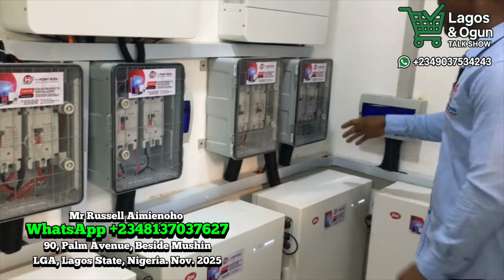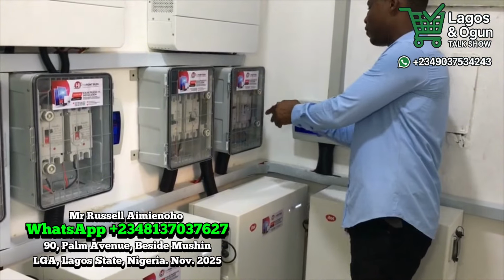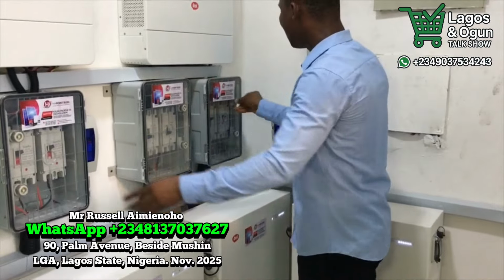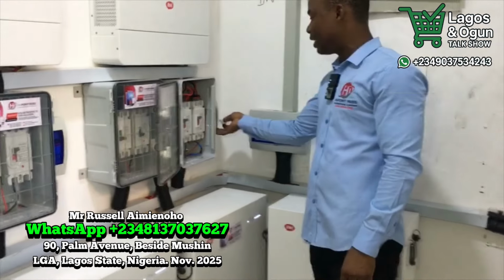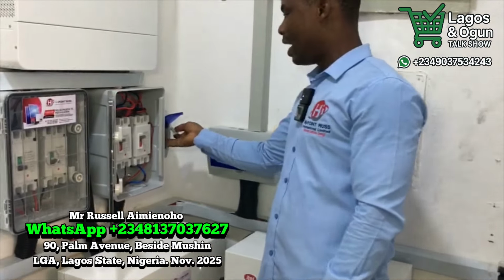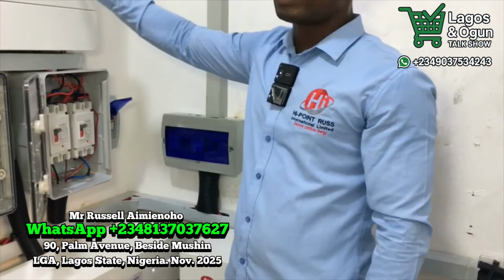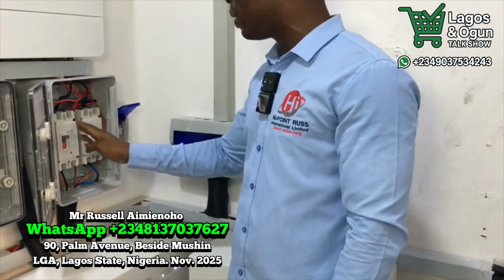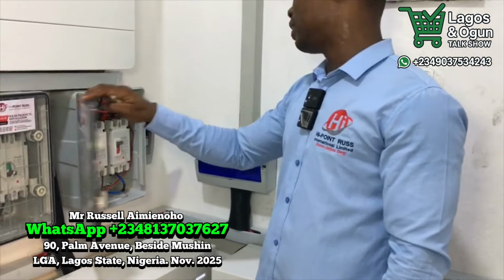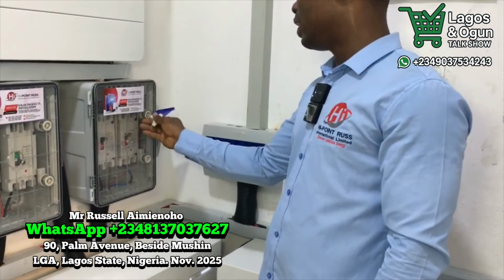Let me lock it back so nobody invades my property here. So that's the second breaker, the last one for the PV here. This one also has its own SPD by the side, with the same settings, because there are two charge controllers inside this inverter, charge controller one and two, and the SPD is also by the side.